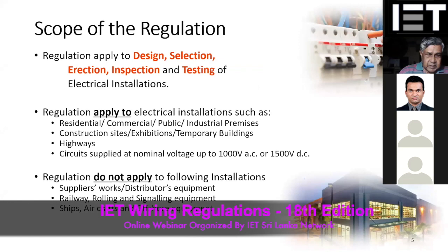Now, when you look at this regulation, sometimes people think that this is the only standard we have to follow. But it is not like that, because the electrical installation nowadays complies with many things. The IET wiring regulation basically applies to the design, selection, erection, inspection, and testing of electrical installations. And it also clearly mentions what types of installation the regulation applies to, and where we cannot apply it. So it applies to residential, commercial, public or industrial premises, or any construction site, exhibition, temporary building, or even a highway, where the nominal supply is less than 1000 volts AC or 1500 volts DC.